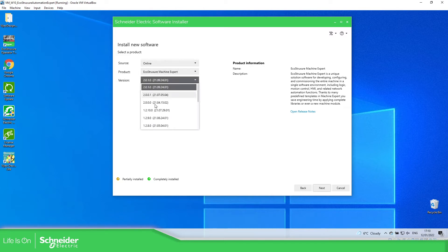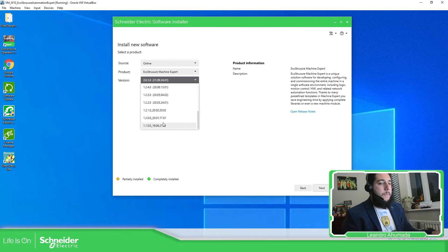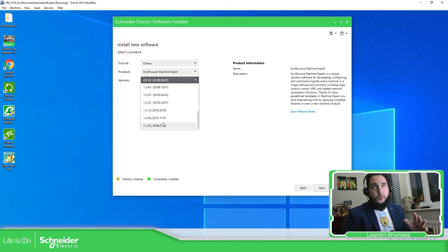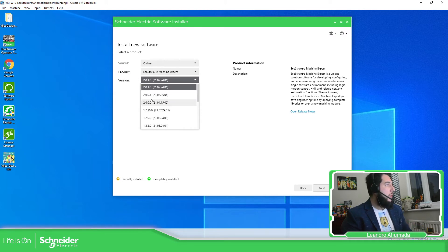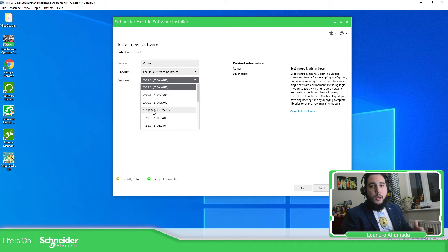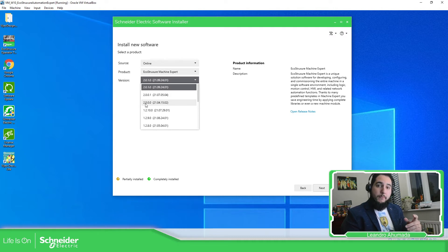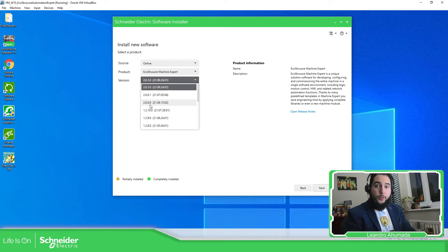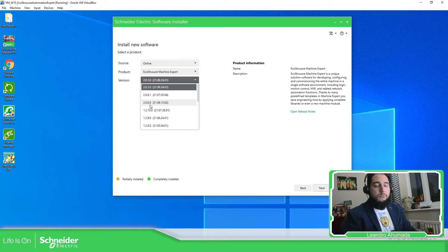We just need to select the version that we want. Here is something important: depending on the version, we have different PLCs. For example, if you want to program the Modicon M258, probably the latest version you can use is EcoStruxure Machine Expert 1.2. On version 2 of Machine Expert, we don't have that PLC, so be aware of which one you need to use. But if you use the M241, M251, M262, or the Lexium pack drive offer, then you can use any of these versions.